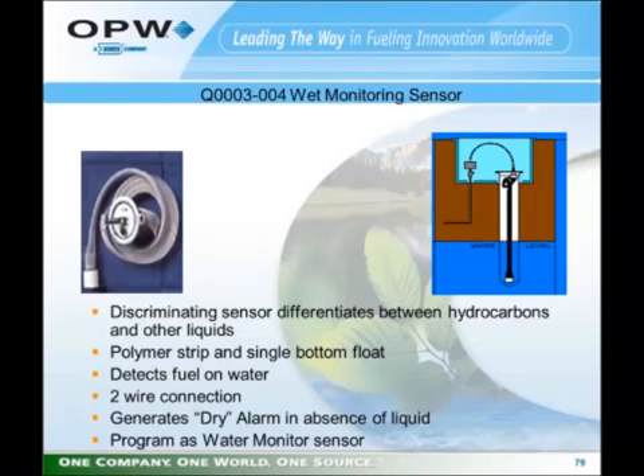The Q0003-004 is a wet monitor well sensor. This is a discriminating sensor that will differentiate between hydrocarbons and other liquids. It is designed to be installed in a wet well. It has a polymer strip that goes down the length of the sensor. It has a water float at the lower end of the sensor. So any hydrocarbons that are floating on the water will be detected by the polymer strip. Should the water go below the bottom of the sensor, that water float will change position. The system will then indicate a dry alarm. What a dry alarm means is your sensor is not functioning because there is no water for the hydrocarbons to be floating on top of. In the unit, this is programmed as a water monitor sensor.